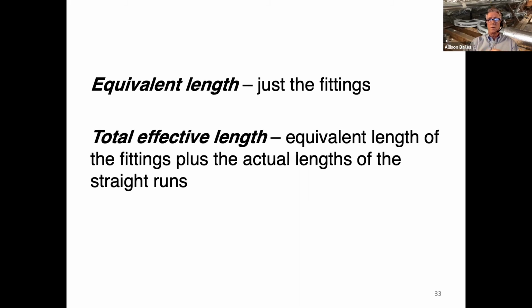So in Manual D, which is the Air Conditioning Contractors of America protocol for designing duct systems, the way we characterize the resistance in a duct system is this thing called total effective length, which has two components: the equivalent length and the straight length. Now, notice there's two different words there: equivalent length and effective length, but they're used differently. Equivalent length is just for the fittings. That's the resistance in a fitting, and it's the pressure drop in the fitting that's equivalent to the pressure drop in a certain straight length of ductwork.